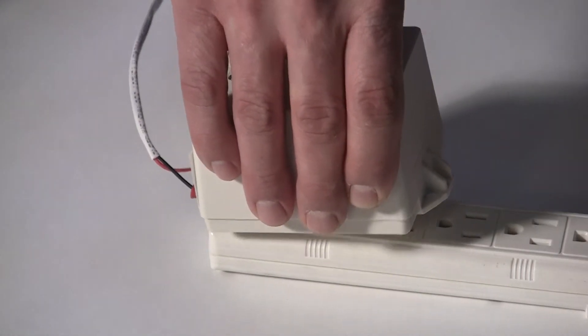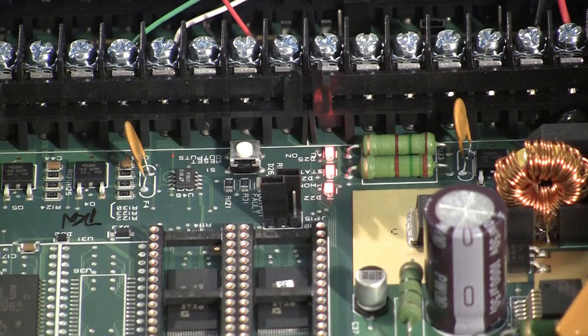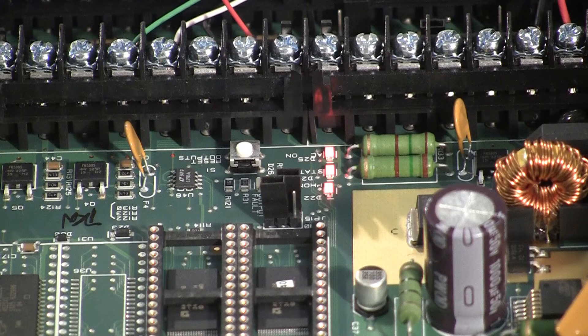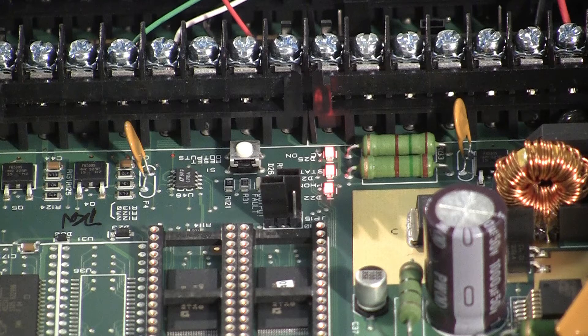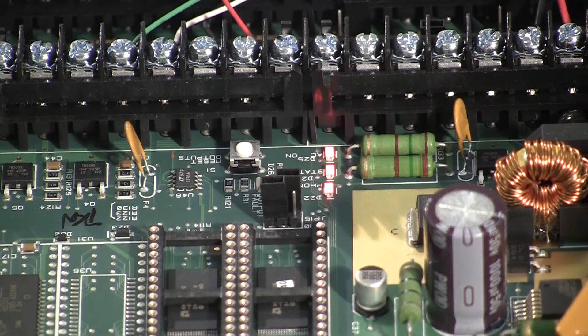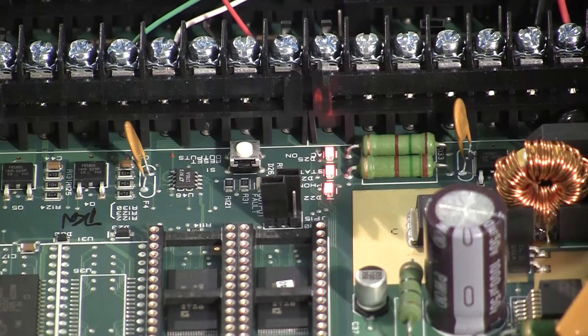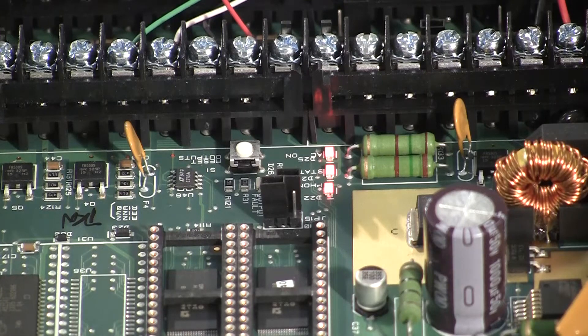Now we are going to power up the system by plugging in the 24VAC transformer. On initial power up you should notice the AC LED will come on solid. After approximately 15 to 20 seconds, the status LED should begin blinking once per second.